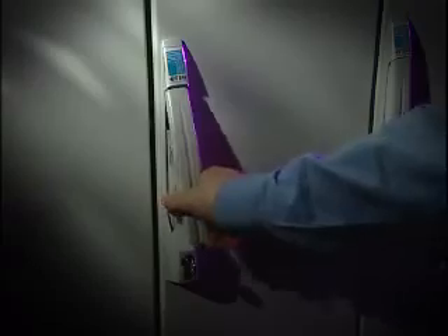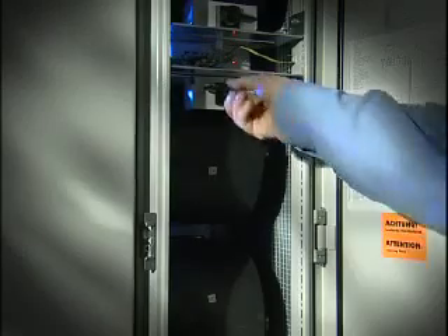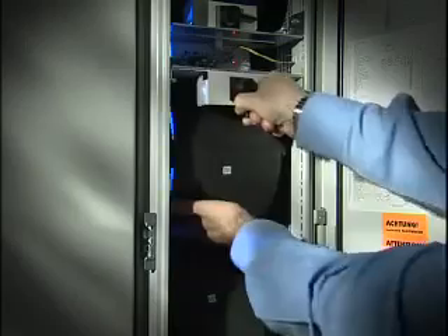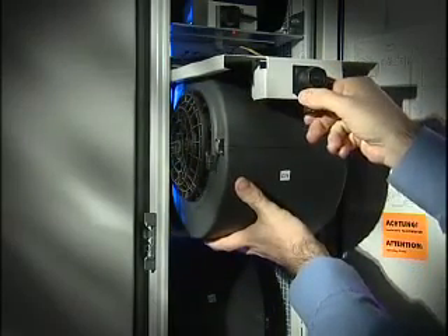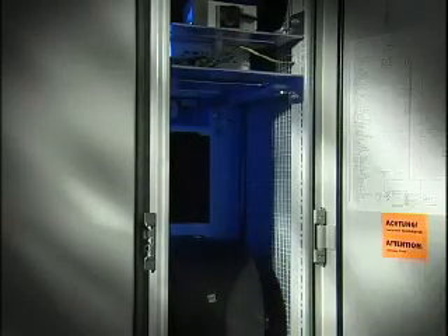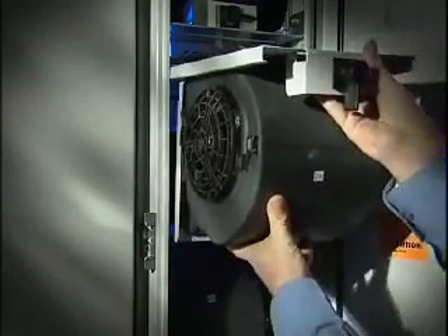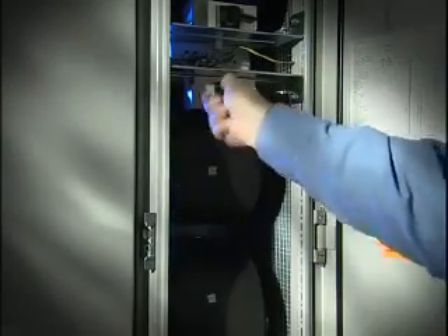The fans that push the air through the heat exchanger are fed from a single 3-phase supply, 2 fans per phase. Therefore, in the event of a phase failure, 2/3 of the fans are still working. The remaining fans will automatically speed up to compensate for the 2 that have shut down. Each fan module is hot swappable and can be removed and replaced in seconds, minimizing the mean time to repair and maximizing the mean time between failure was one of the key design considerations for LCP Plus.